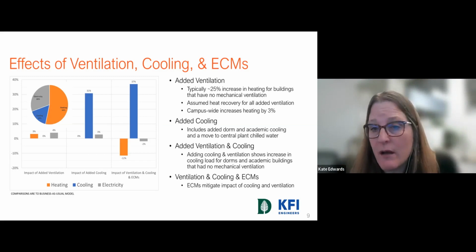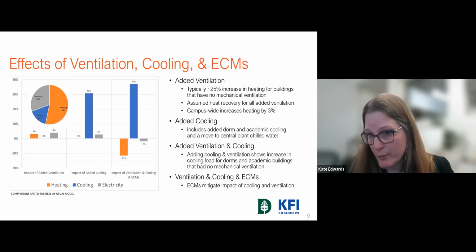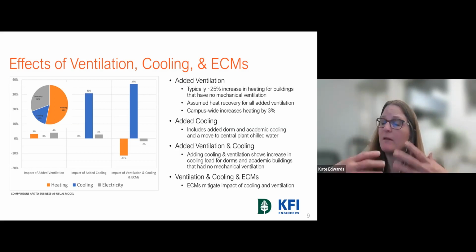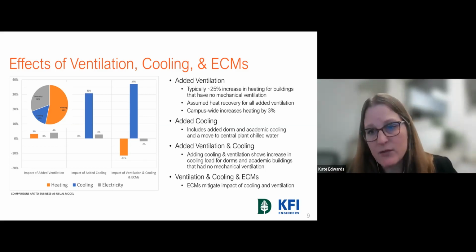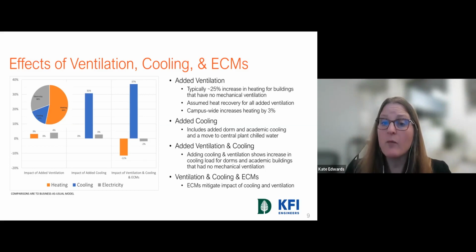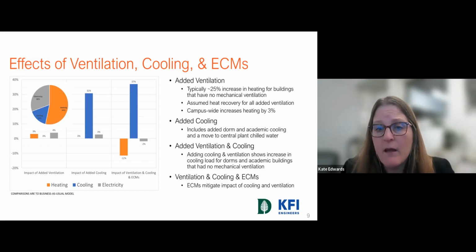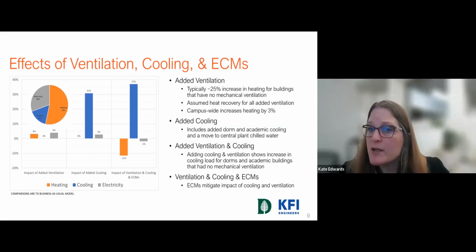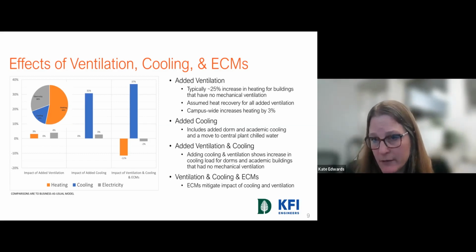That is the addition of ventilation to bring buildings constructed under previous codes up to current standards. We're assuming Dartmouth will bring all buildings up to current ASHRAE 62 standards for mechanical ventilation. We're also assuming cooling will be added to dorms and academic buildings. Some buildings have existing window air conditioner or standalone systems, and those will also be transitioned onto the central campus chilled water system.